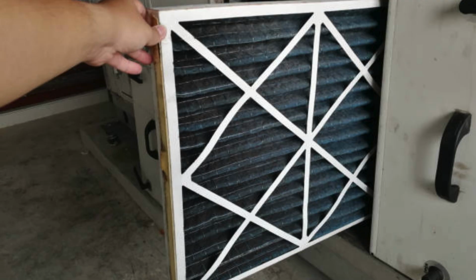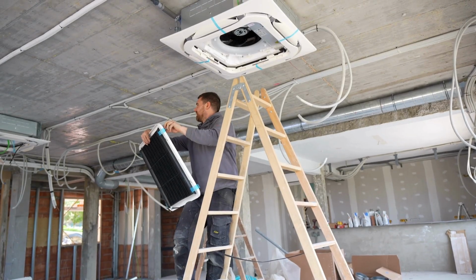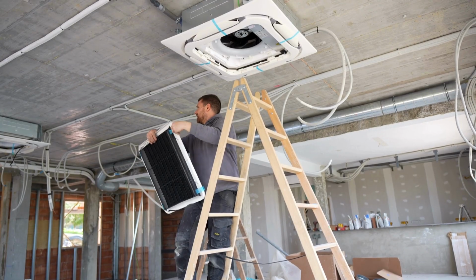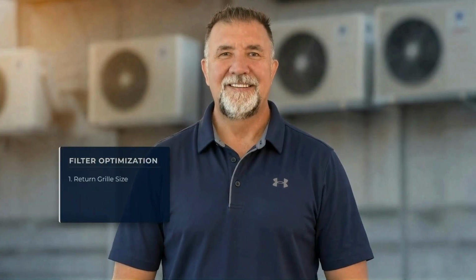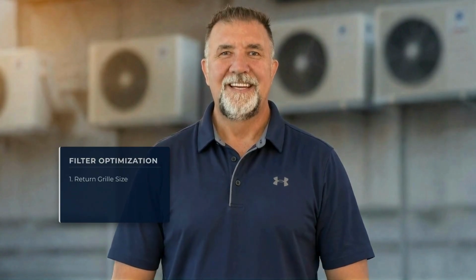If you're not sure and you don't want to go through all this stuff, I would recommend MERV 8 to MERV 10 max until you have the system checked out to let you know what your available static pressure is. Well, the size of the filter is determined by the return grille, which can always be made bigger. And if you have a bigger filter, what did we just talk about? If you have a bigger filter, you have more surface area. More surface area means that you may be able to go with a higher efficiency filter.